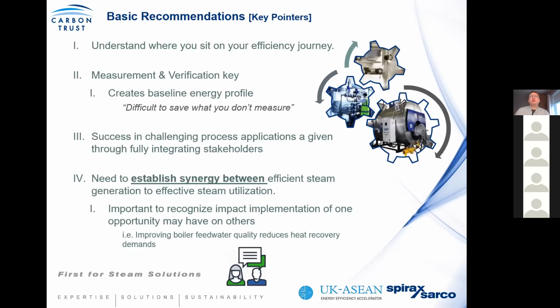So we're going to give you some basic recommendations. What you need to do is understand your current system and where you sit on that sustainability or efficiency journey. Dave mentioned earlier about traps and meters, especially meters, because what we're finding is that the need to validate and ensure that you've achieved savings is becoming very key. So measurement and verification is important, but what we're also finding is the accuracy of some metering is quite poor because installed meters have become damaged due to the water hammer issues or erosion problems we spoke about.